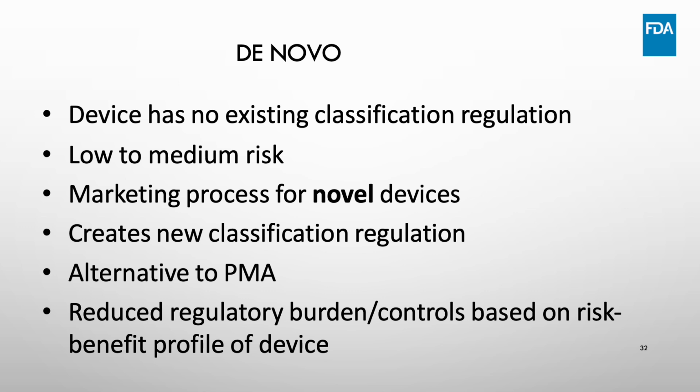A de novo may be considered an alternative to the PMA. The benefit of the de novo is to regulate the new device type with a reduced regulatory burden compared to that of a PMA.